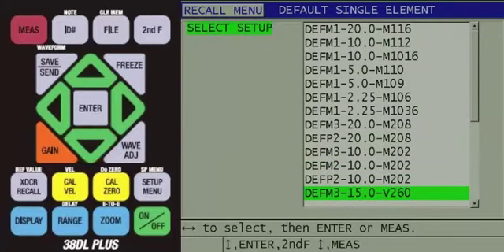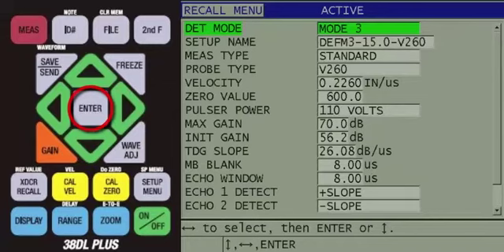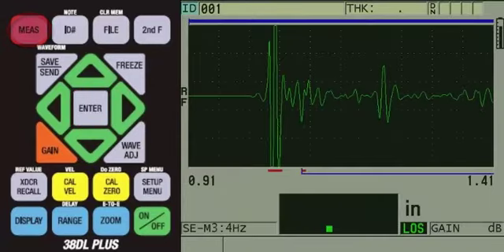DEFM 3-15.0-V260. At this point, you can press the red Measure key to recall the setup, or press the Enter key to see the parameters within the setup. If you press Enter, press the red Measure key next in order to recall the setup and return to the measurement screen. The default setup we recalled has a default sound velocity for stainless steel, so we need to change it to something closer to aluminum.